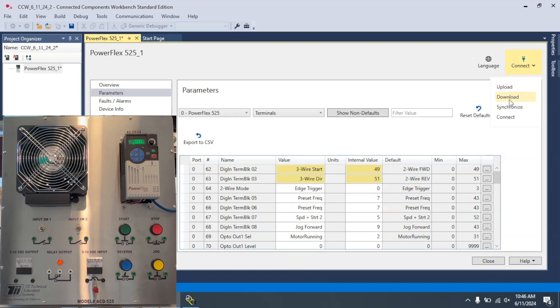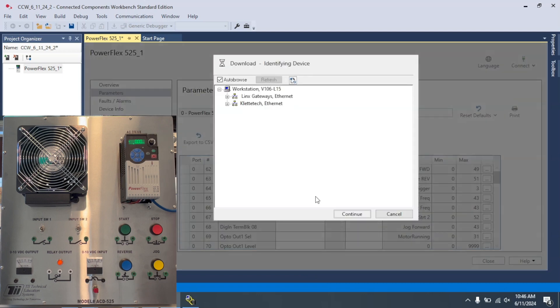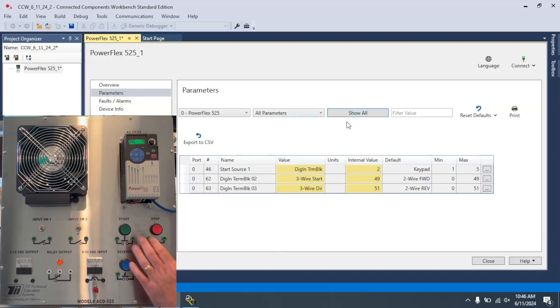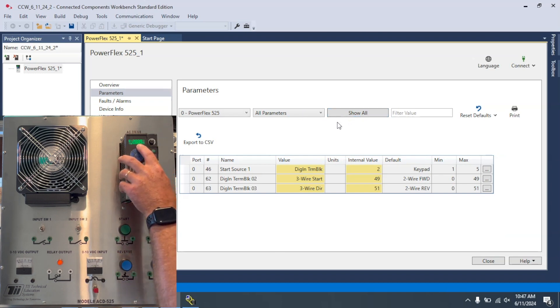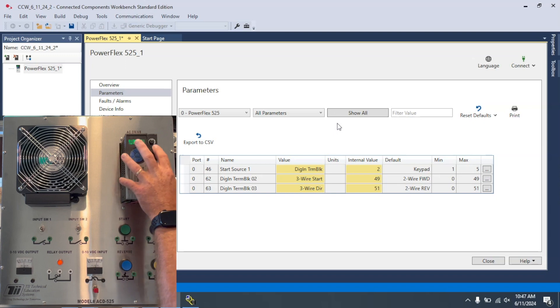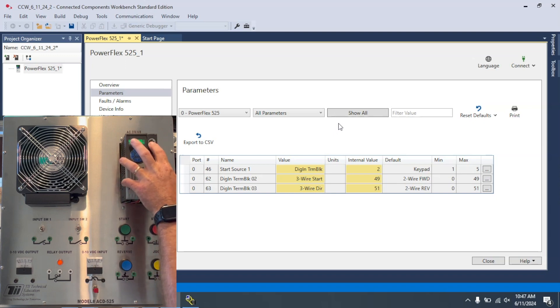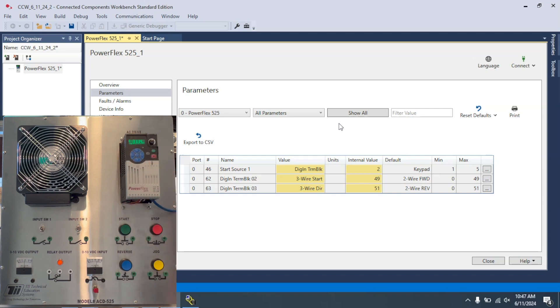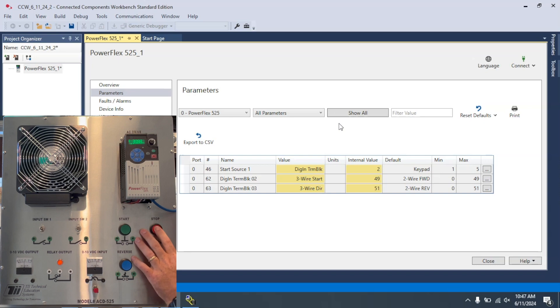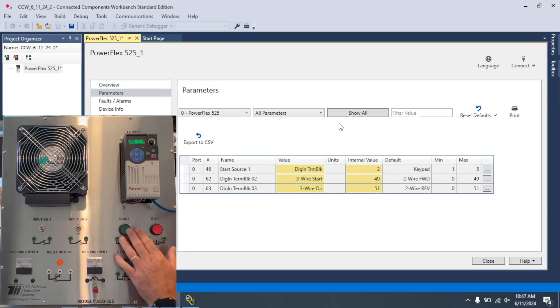So, I'll come here. I'm going to download this. Activate my Start button. This will run to whatever frequency my keypad potentiometer is set to. And I can adjust this here. So, I'll let this settle in at around 31 hertz. And if I activate the Stop button, this shuts down the VFD.